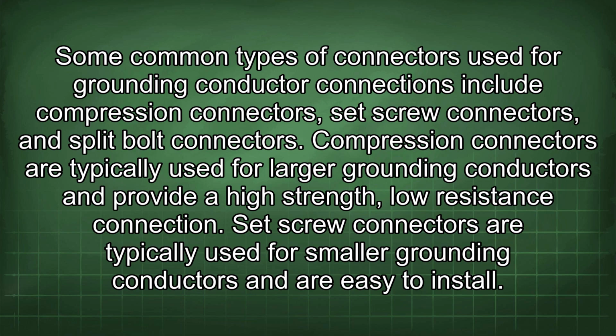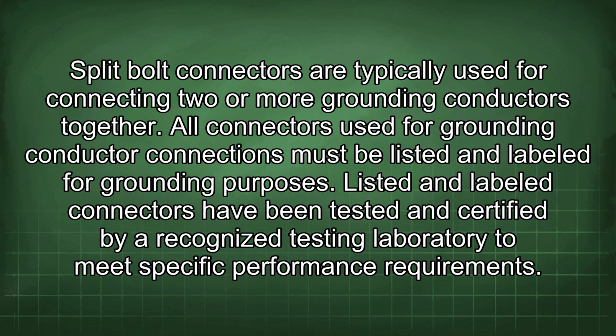Compression connectors are typically used for larger grounding conductors and provide a high-strength, low-resistance connection. Set screw connectors are typically used for smaller grounding conductors and are easy to install. Split bolt connectors are typically used for connecting two or more grounding conductors together. All connectors used for grounding conductor connections must be listed and labeled for grounding purposes. Listed and labeled connectors have been tested and certified by a recognized testing laboratory to meet specific performance requirements.